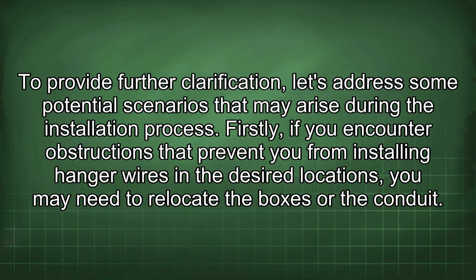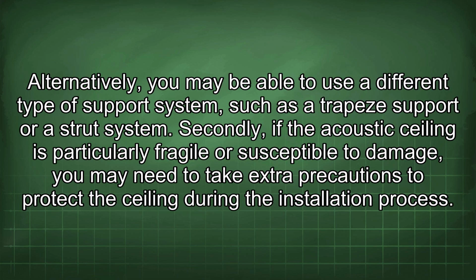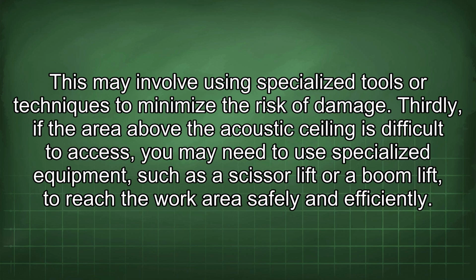To provide further clarification, let's address some potential scenarios that may arise during the installation process. Firstly, if you encounter obstructions that prevent you from installing hanger wires in the desired locations, you may need to relocate the boxes or the conduit. Alternatively, you may be able to use a different type of support system, such as a trapeze support or a strut system. Secondly, if the acoustic ceiling is particularly fragile or susceptible to damage, you may need to take extra precautions to protect the ceiling during the installation process. This may involve using specialized tools or techniques to minimize the risk of damage.